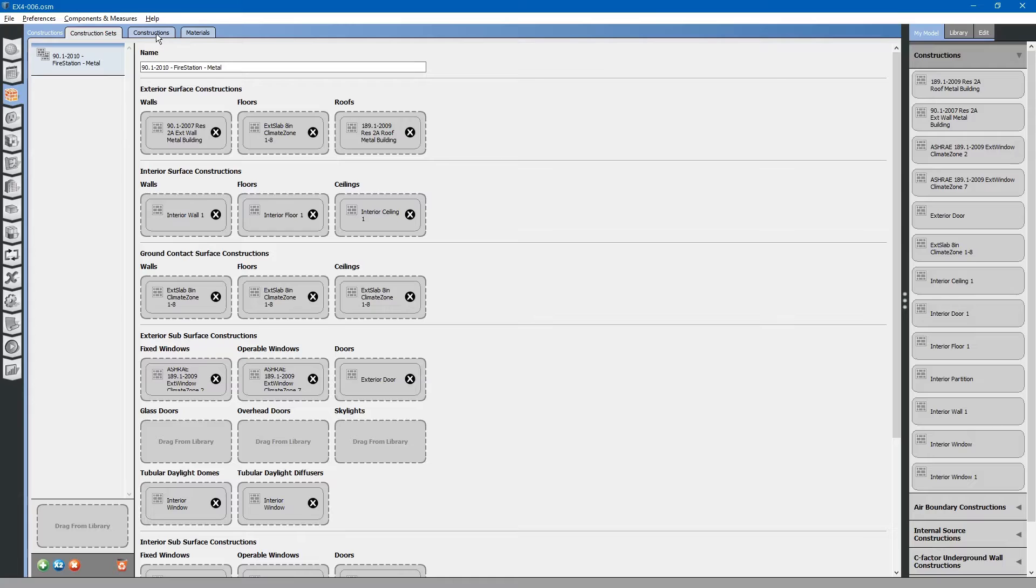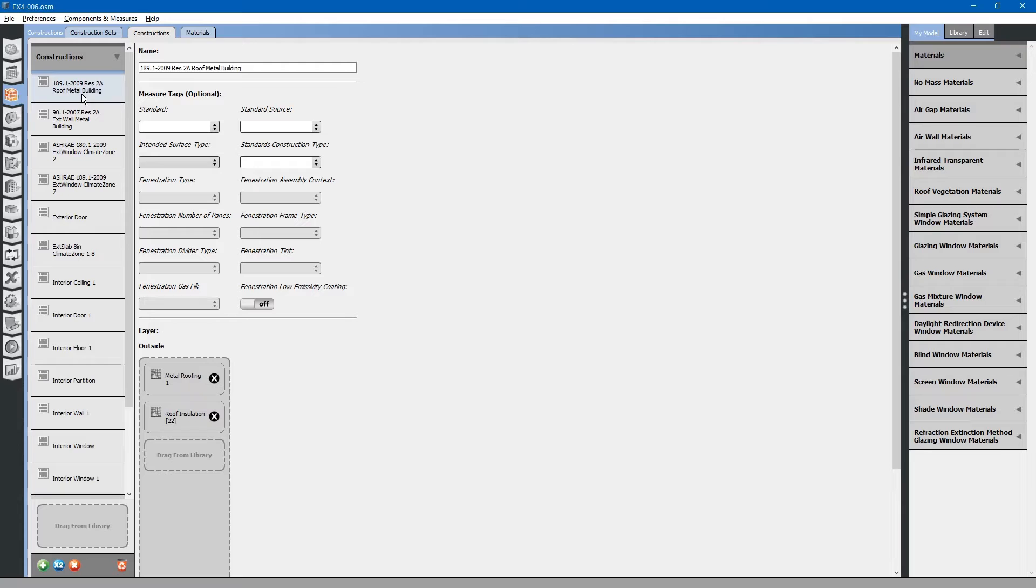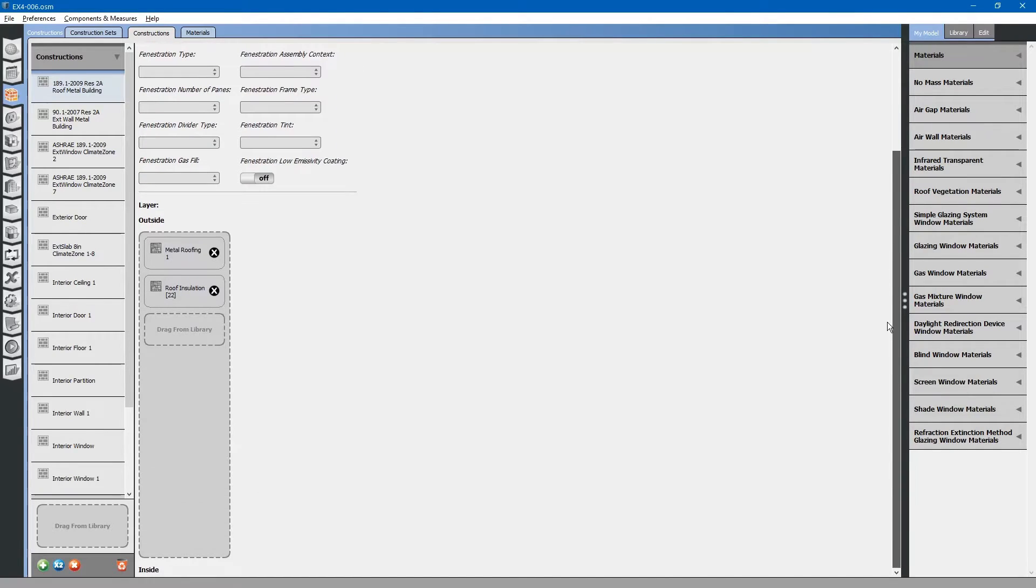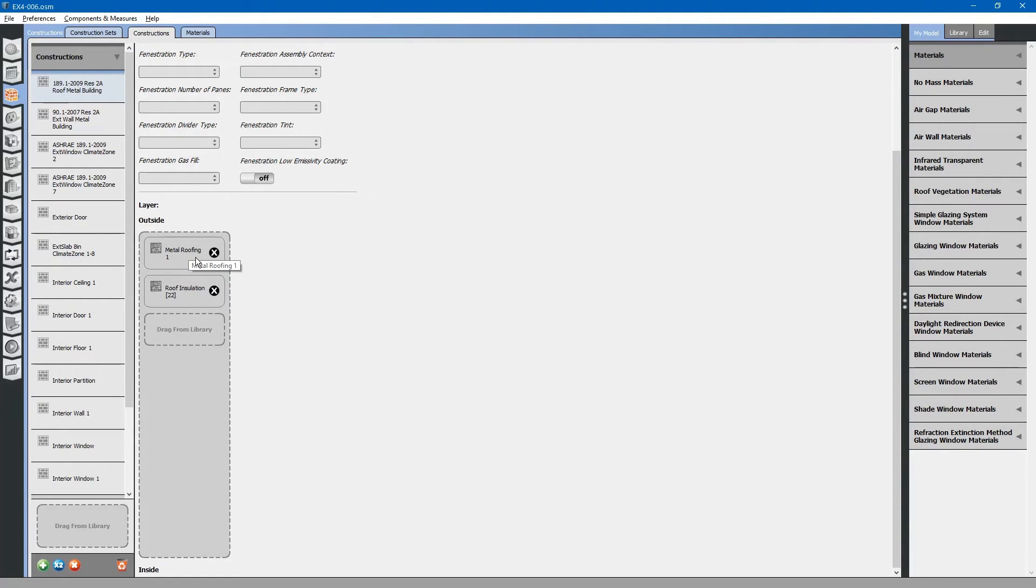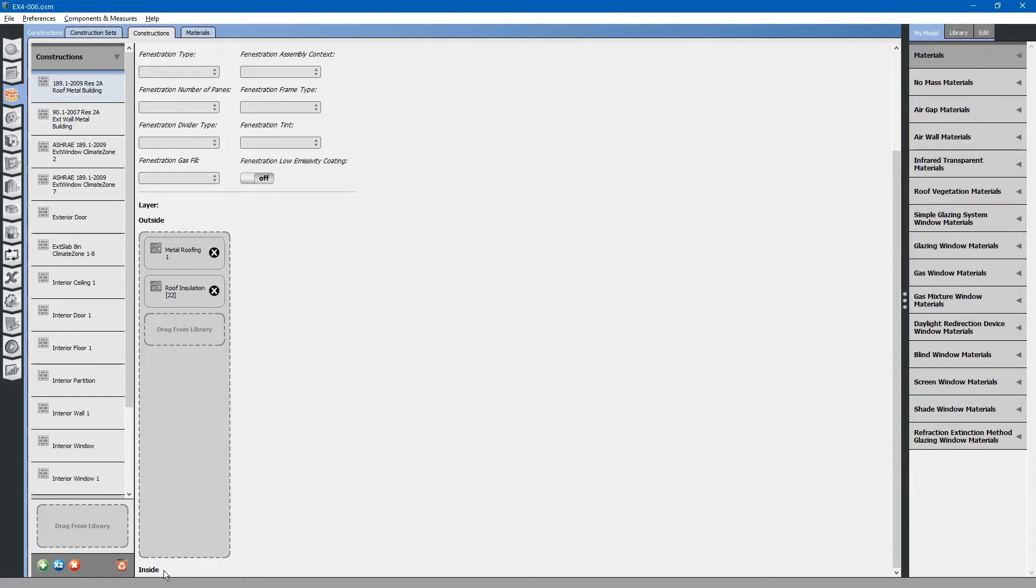Next, let us look at the constructions tab. The constructions tab shows construction assemblies. We will look at the first one, metal building roof. The metal building roof is comprised of metal roofing and roof insulation. You will see that these materials are applied in layers because they will be used to calculate the thermal conductivity and heat transfer properties of this construction assembly. The layer starts on the outside, metal roofing, and moves inward, roof insulation, inside the building.